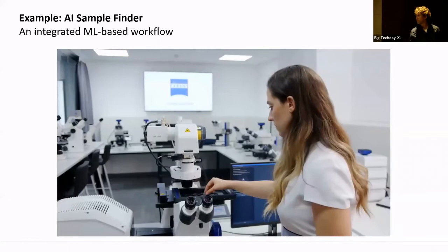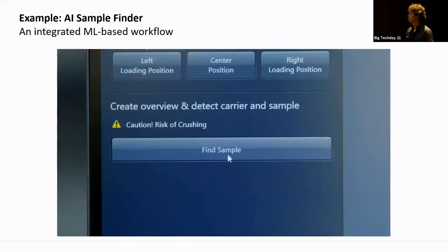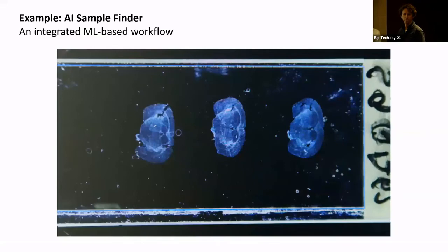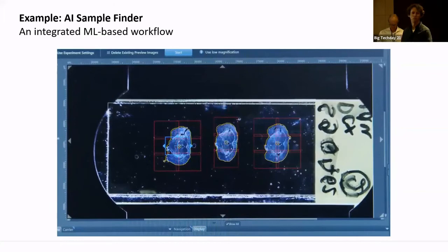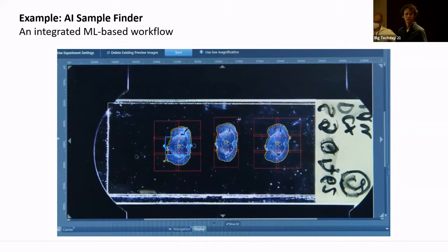A typical scientist puts a sample on the microscope and presses 'Find Sample.' The AI starts working in the background. Some images are taken from the sample with a fancy LED, and the AI checks the image — first figuring out what kind of sample carrier it is: a slide, a petri dish, a well plate. It automatically detects what you're interested in and converts this into an experiment. All the work of finding the sample, finding it, and focusing it is done by AI in the background.